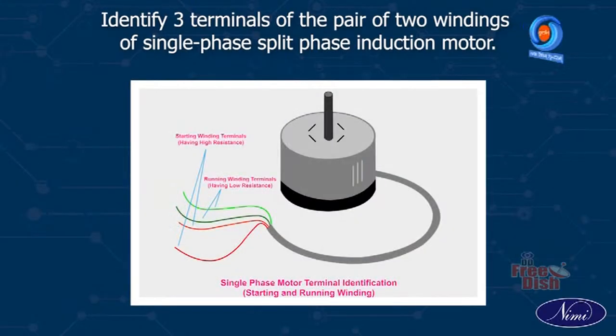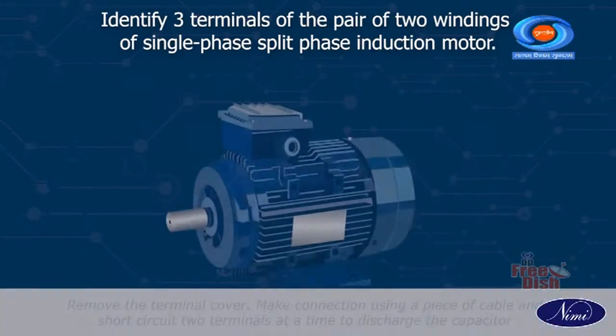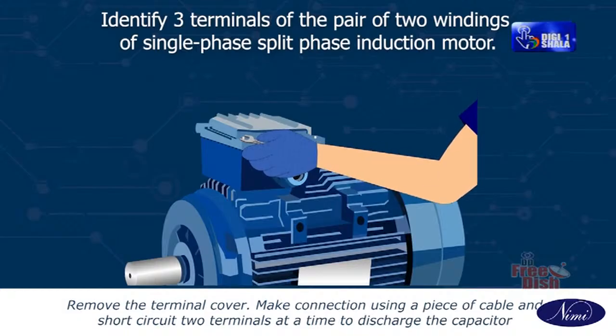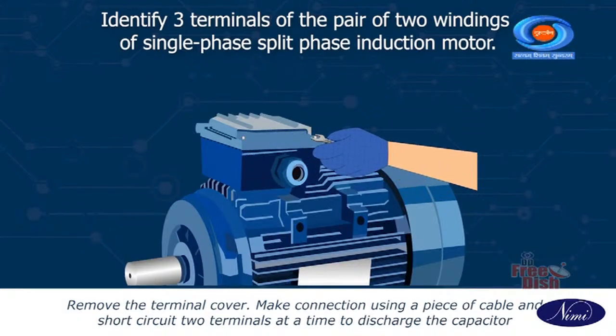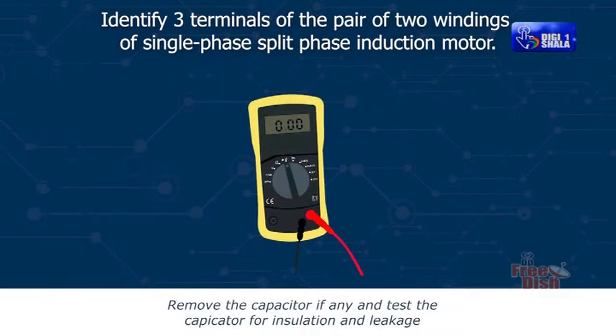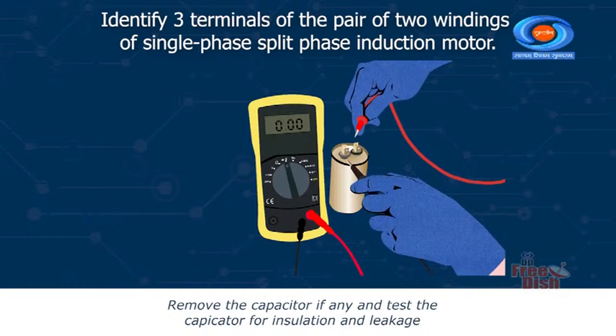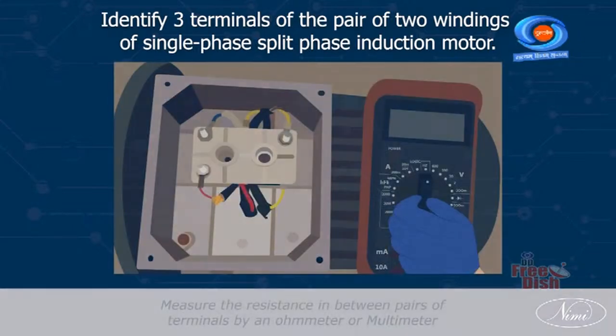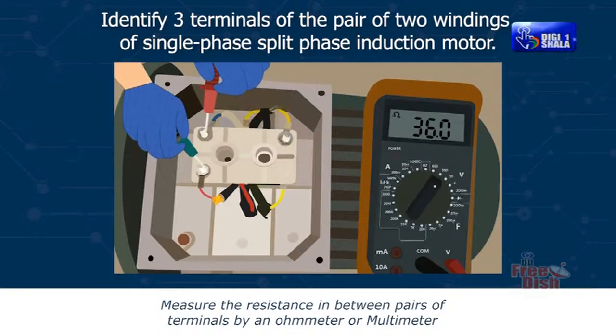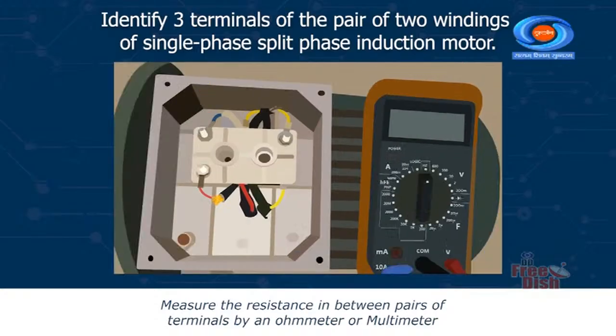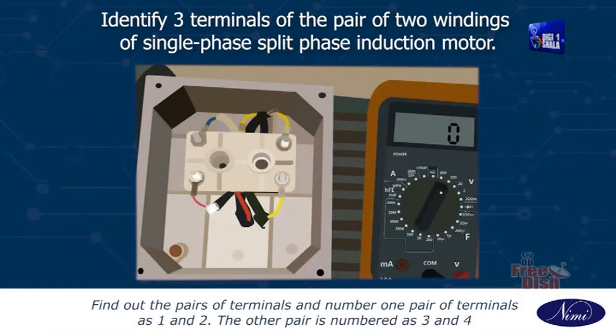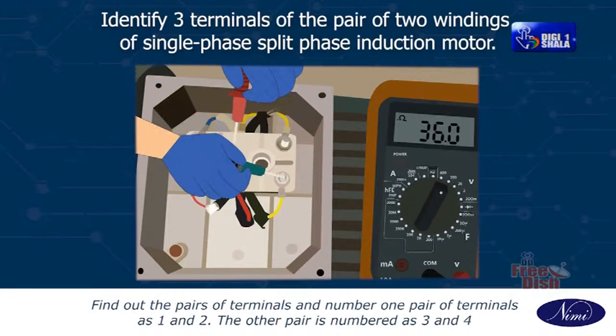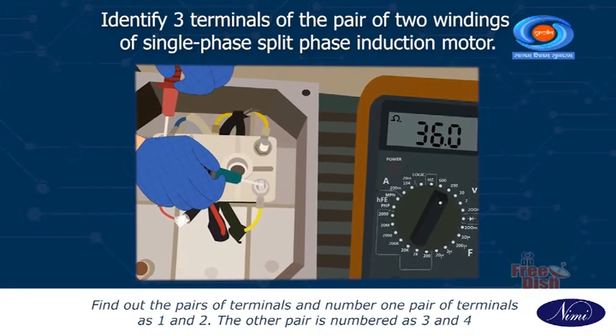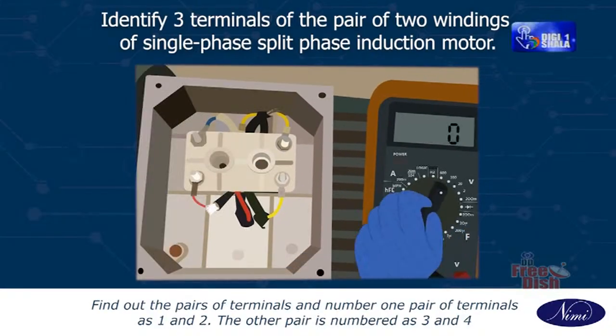Identify 4 terminals of the pair of 2 windings of single phase split phase induction motor. Remove the terminal cover. Make connection using a piece of cable and short circuit 2 terminals at a time to discharge the capacitor. Remove the capacitor if any and test the capacitor for insulation and leakage. Measure the resistance in between pairs of terminals by an ohm meter or multimeter. Find out the pairs of terminals and number 1 pair of terminals as 1 and 2. The other pair is numbered as 3 and 4.